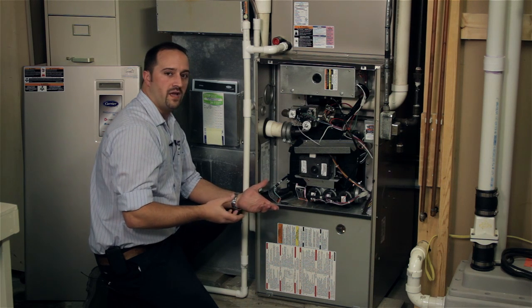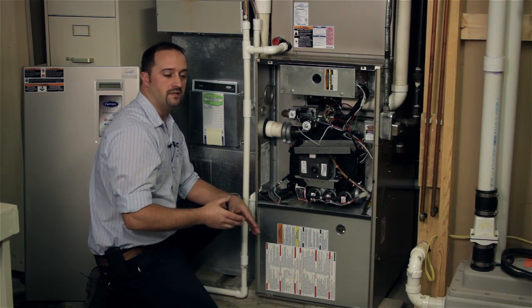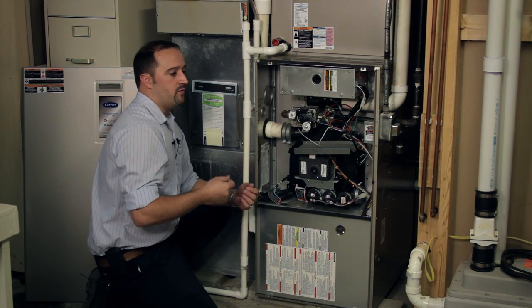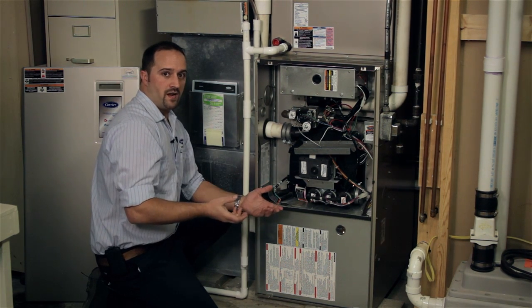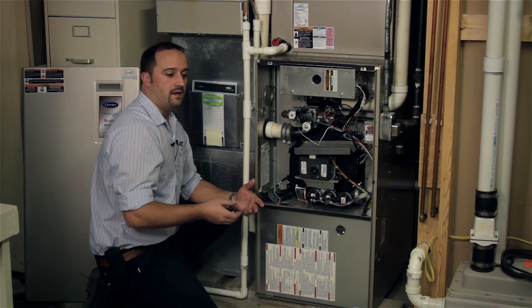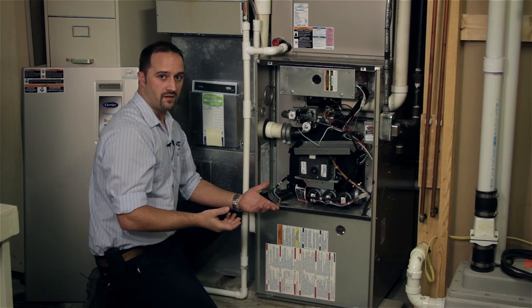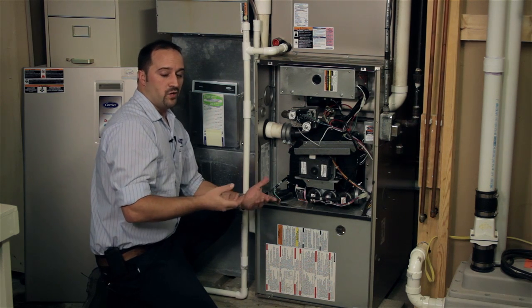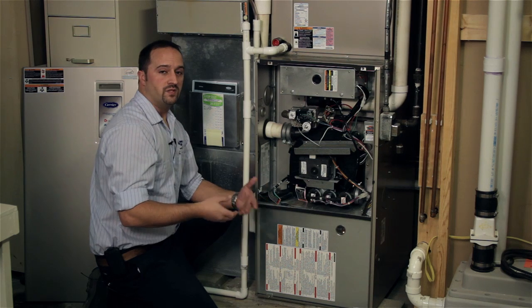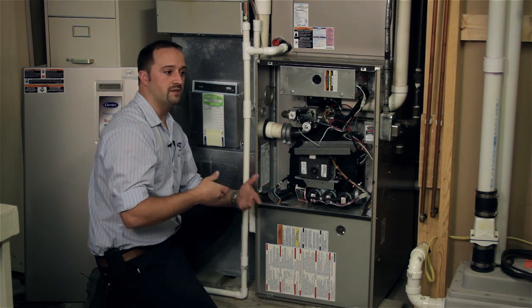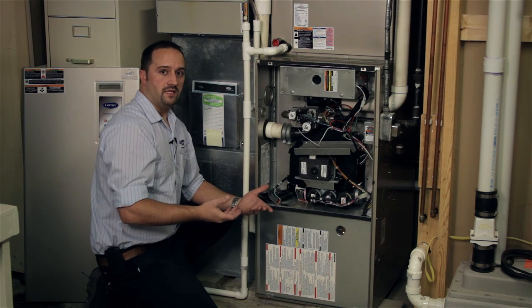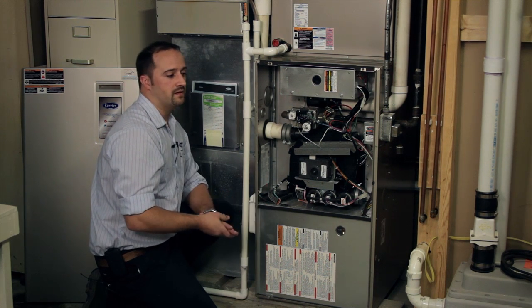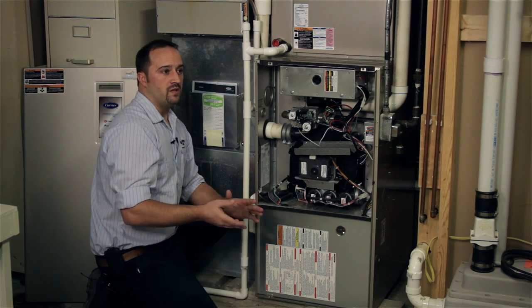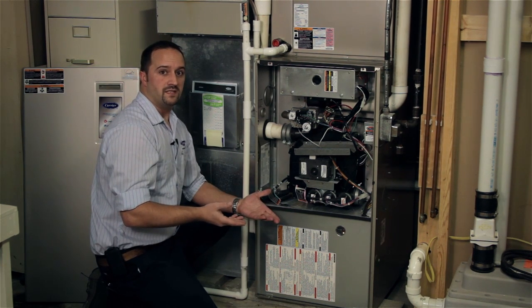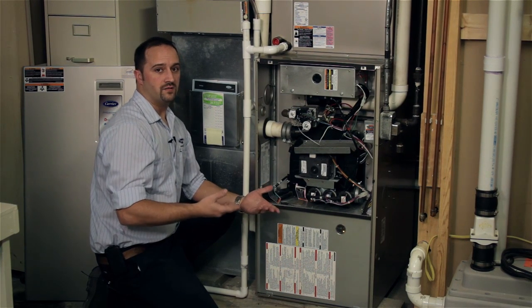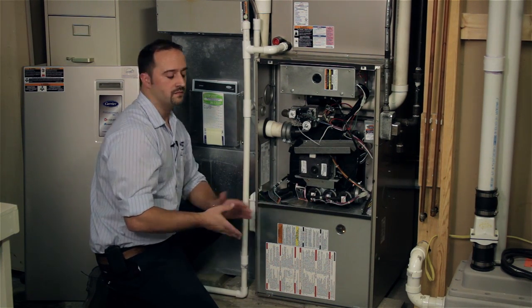A cracked heat exchanger will actually allow carbon monoxide to get into the house, and that is the silent killer. I will put a little plug in here that if you don't have a carbon monoxide detector, I really suggest you get one. I recommend spending the money on one because this is your life that we're talking about. We don't want you to go out and buy Joe Bob's home CO detector. We want you to buy a good name brand, a Carrier brand, a Honeywell, something that is a name brand that has quality and has some good standards behind its production. Carbon monoxide detectors normally last for about 5 to 7 years, so you can expect to replace it within that time frame. But once again, it is your life that we're talking about here, and it is worth the investment.